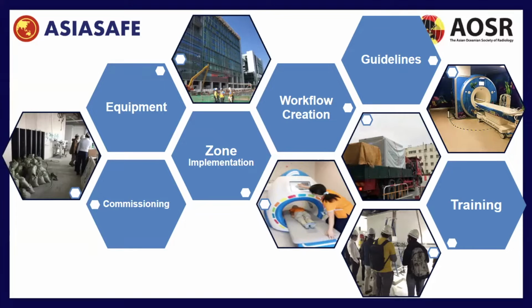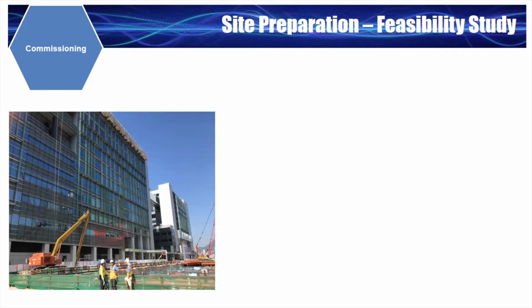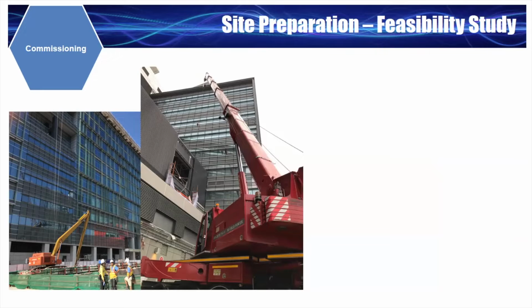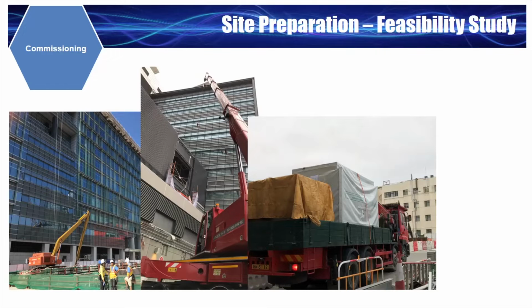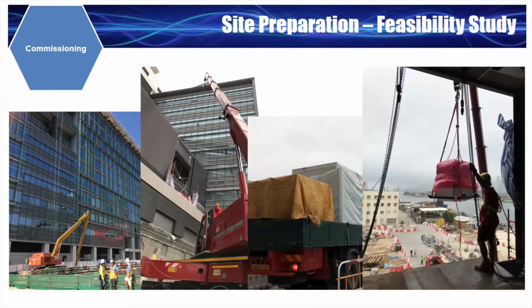In this presentation, I'd like to share with you our experiences on commissioning, equipment, zone implementation, workflow creation, guidelines, and training. On March 6, 2018, our 1.5 Tesla MRI scanner was delivered. Wall panels were purposefully built at this location to allow for installation. They were removed. At 6 a.m., the magnet arrived. It weighed 4,500 kilograms, and it is through this wall panel that the MR was delivered.